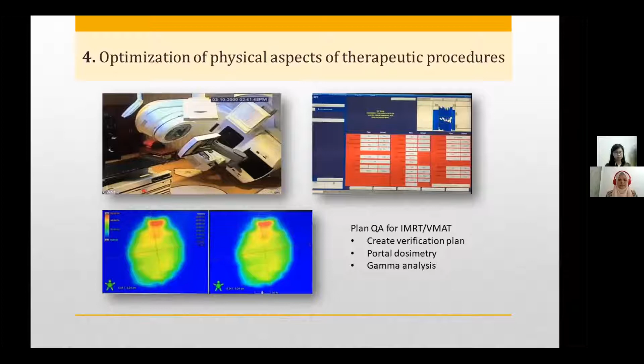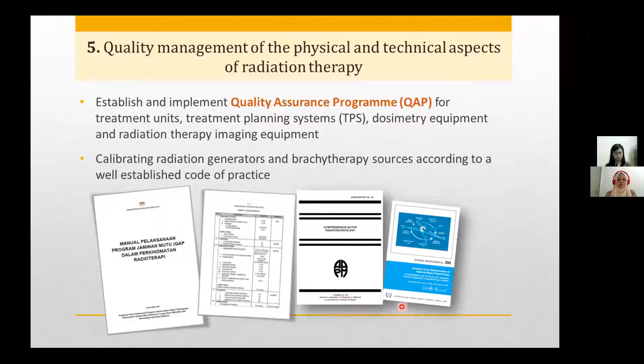Number 5, quality management of the physical and the technical aspect of radiation therapy. Establish and implement a quality assurance program for treatment units, TPS, dosimetry equipment, and radiation therapy imaging equipment. Also calibrate radiation generators, which are LINACs, and brachytherapy sources according to a well-established code of practice. For example, this is a QAP manual from our Ministry of Health, and also international guidelines such as from AAPM and IAEA. Some examples for the machine QA.